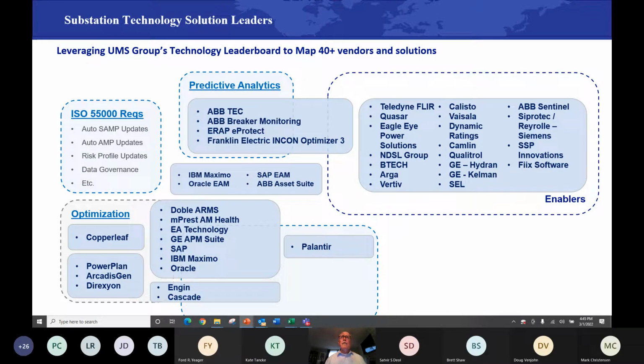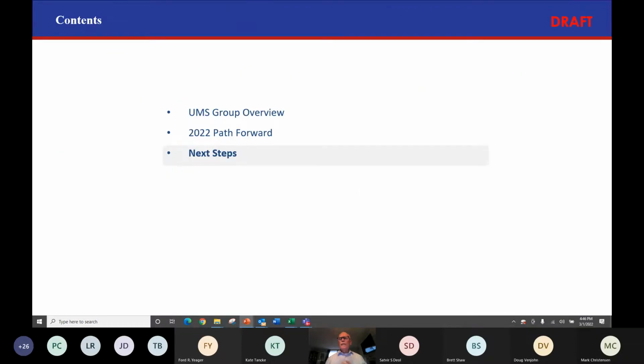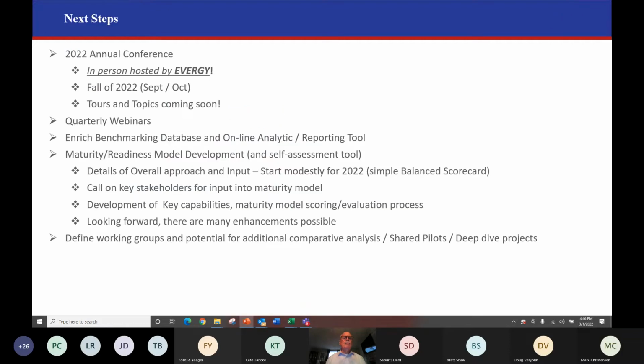I know that if we extend into new technologies, there are new sensor technologies for infrared, for partial discharge, for using LiDAR in new ways. If we bring in companies that make sensors detecting new anomalies, vibration, acoustic monitoring and signature analysis, torque, momentum, all kinds of new sensors are being applied to identifying anomalies in breakers and other assets in substation health. So we'll pull that all together as part of the program this year, and each member of the program will have access to it.